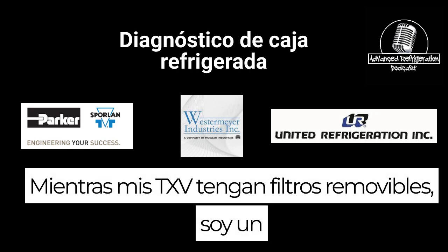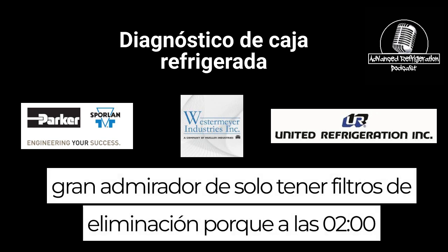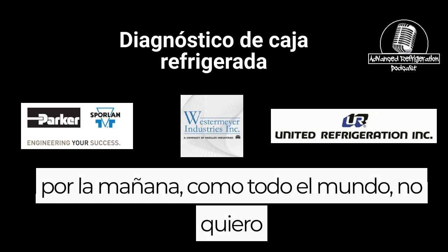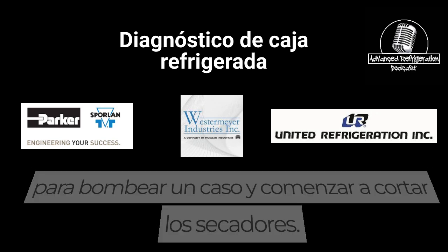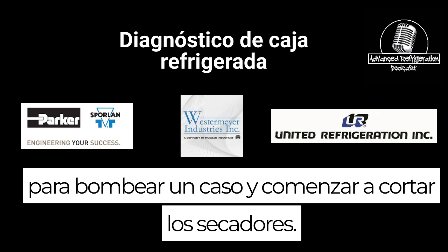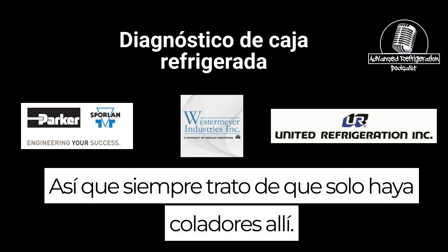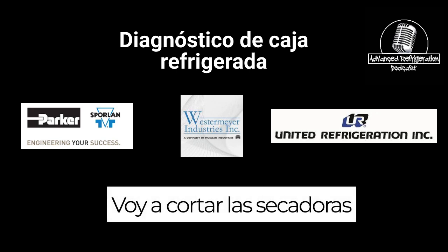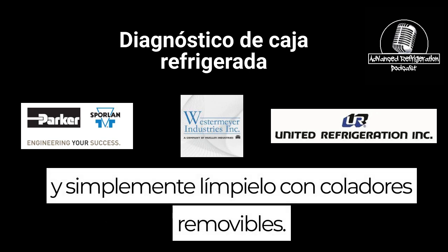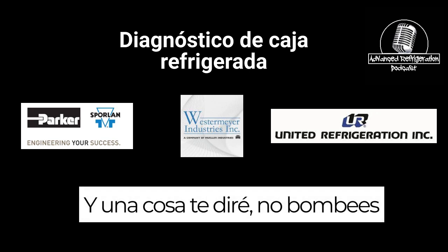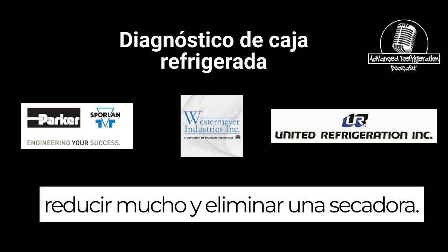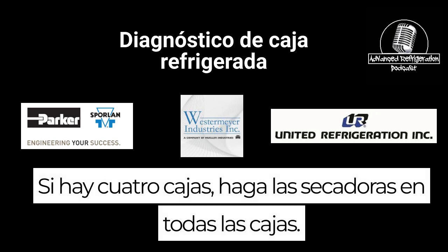As long as my TXVs have removable strainers, I'm a big fan of just having removable strainers, because at 2 o'clock in the morning, just like everybody else, I'm not wanting to pump down a case and start cutting out dryers. So if there's just strainers in there, I'll just cut out the dryers and clean the removable strainers. And one thing I'll tell you guys, do not pump down a line and cut one dryer out. If there's 4 cases, do the dryers on all the cases.